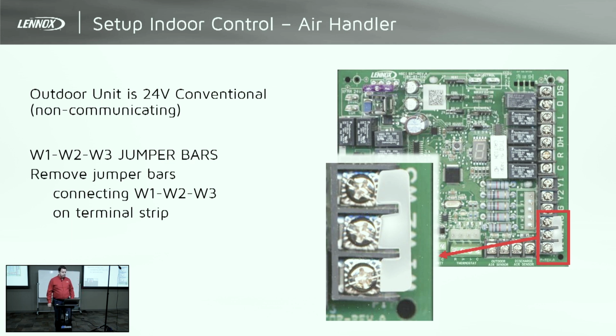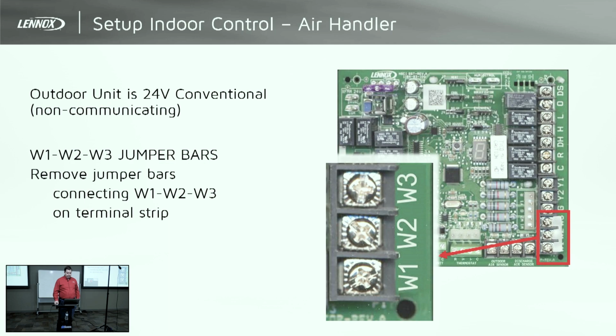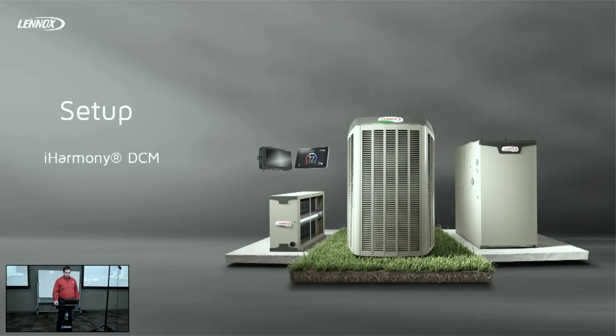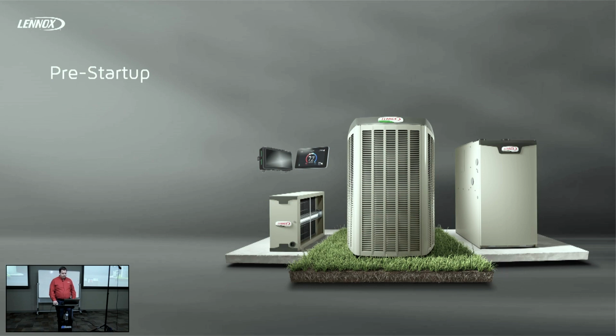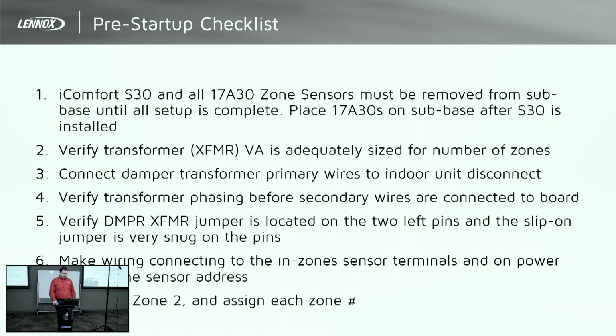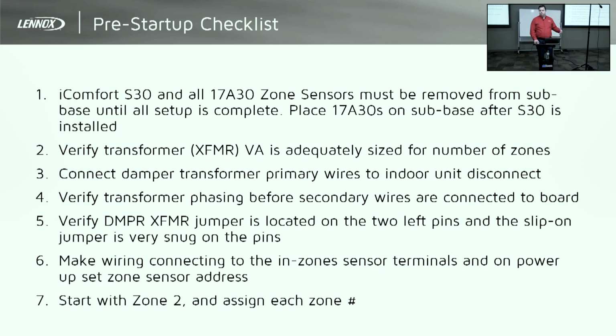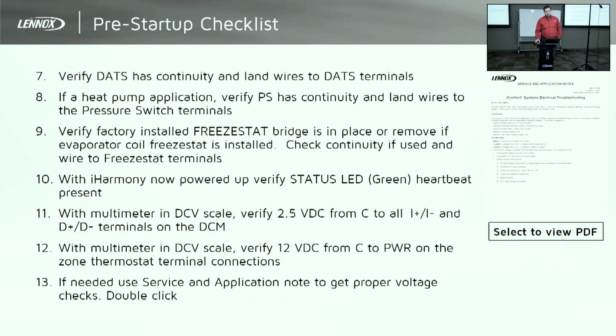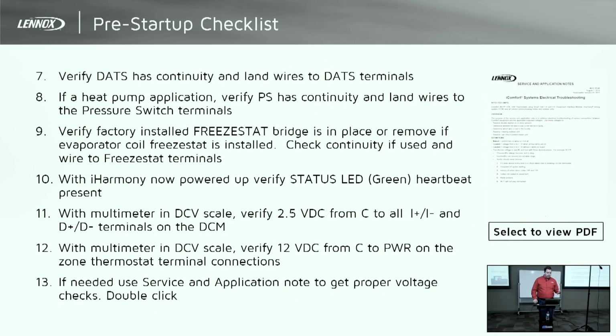On an air handler, of course, again, if you've got multiple electric heat stages, you want to take that little jumper off of there, if you're using like a 15 or 20 kW heat strip on there. So as far as setup's concerned, I know we're running low on time here, but basically going through your wiring, make sure everything's identified properly, installed properly. The phasing on that damper transformer is going to be critical. Making sure that our heat pump pressure switch is installed properly.